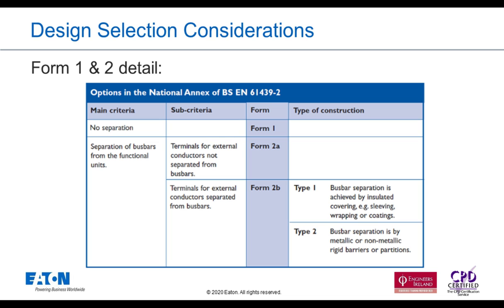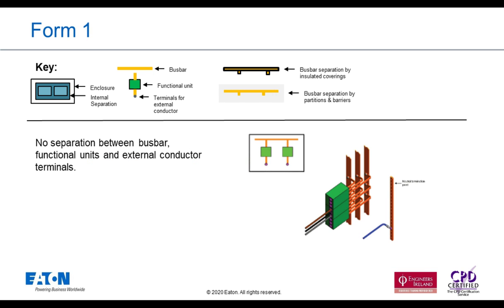There's 2 sub-criteria. Form 2A. Form 2A basically means that you don't need to separate your outgoing cables from the main bus bar. And 2B, you do need to separate. And then you've got the type 1 and type 2, which is how you separate that. So we'll have a look at the next slide, which gives us some graphical representations.